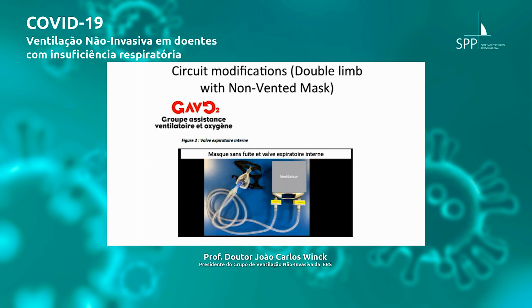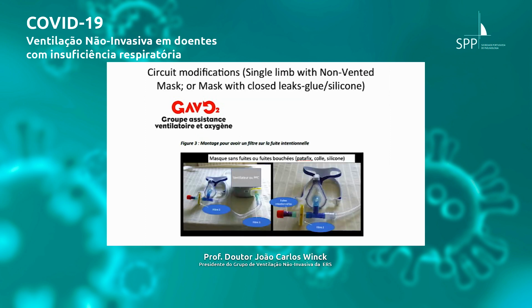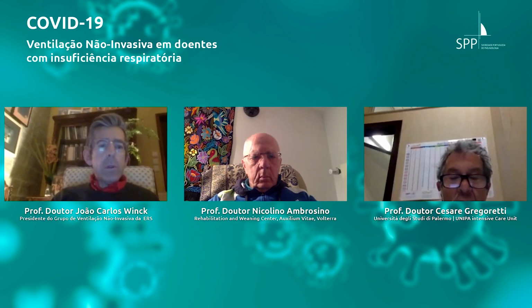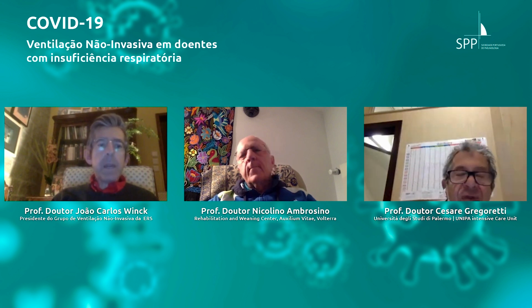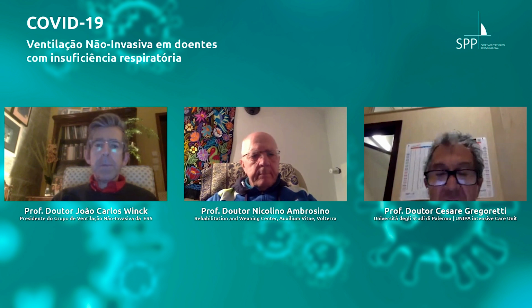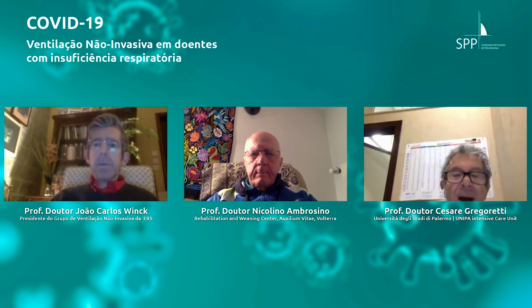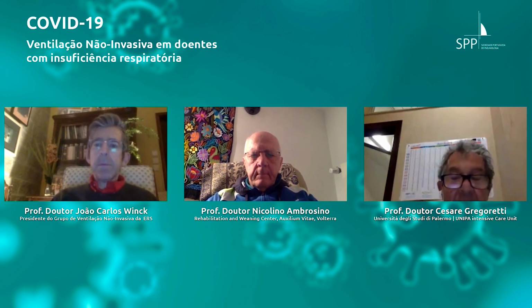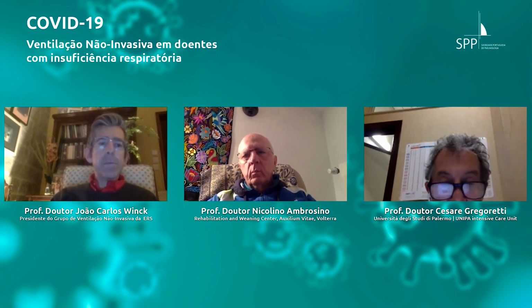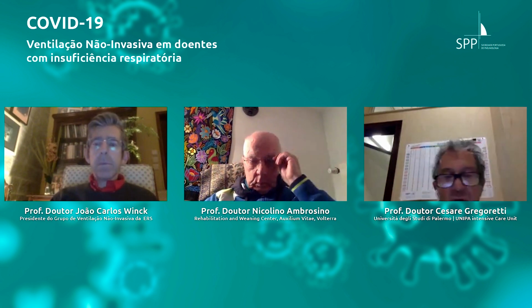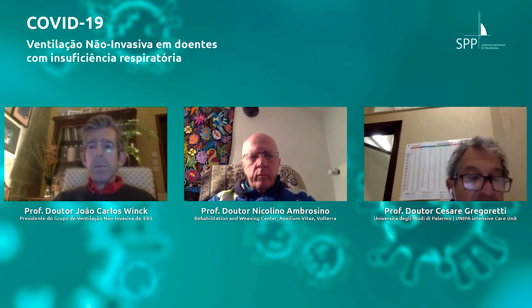Remember, Joao, usually to have a good washout, we need at least a 5 millimeter hole. You have to create a hole by yourself because you are increasing dead space. So you need more flow inside to flush the mask. The bigger the hole, the higher the amount of flow that flushes the system. It's like having a small helmet. You understand what I say? Because remember, you have to avoid an increase of the patient's respiratory drive due to carbon dioxide. Try not to remove the mask from the patient's face if we can, okay? Because the treatment could not be effective.